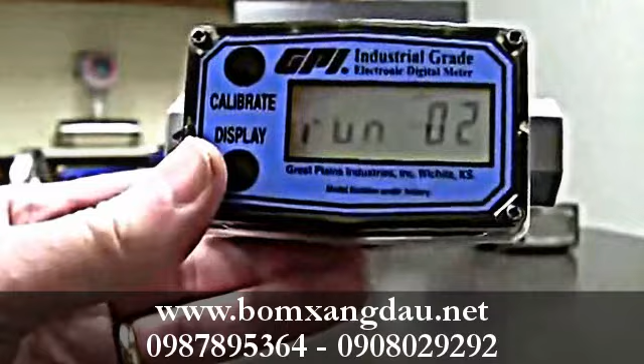Now, I don't want to do the runs at the same flow rate because it's a waste of time. The whole point is, along the entire curve of a meter, you're going to have different K factors for different flow rates. Now, all the K factors are going to be almost identical, but just a little bit different. But if you do several runs at different rates of flow, the display is smart enough to know, okay, I'm going this rate of flow, I'm going to use this K factor. You speed it up, okay, I'm going this rate of flow, I'm going to use that K factor. And it gives you a little bit better accuracy.